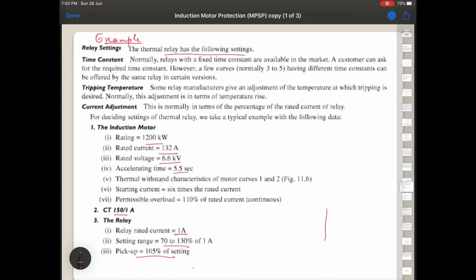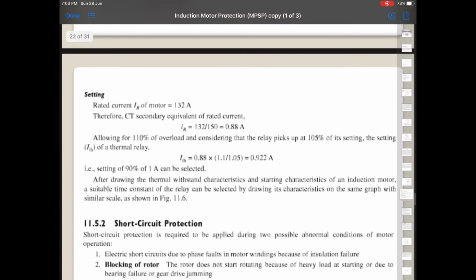Why it is so is because you have a curve something like this, just what we saw, of the relay, and this is of a motor. Since the pickup factor is a dividing factor, we get the point lesser than the current rating of the induction motor.